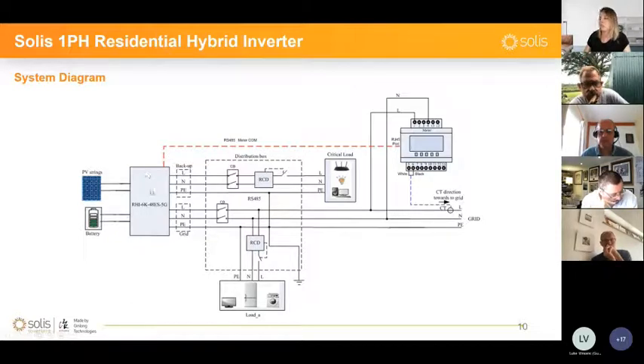The inverter will take its decisions based on this information coming in from the meter. The inverter will decide whether to start charging or discharging the battery in case it detects an export of energy to the grid. So if your hybrid inverter is generating energy and it's more than what the loads are able to consume, then normally this energy will be supplied to the grid.